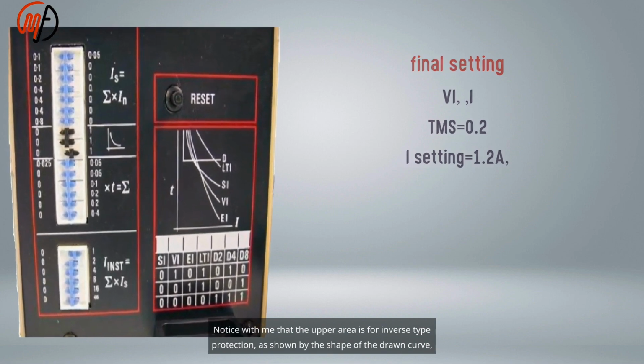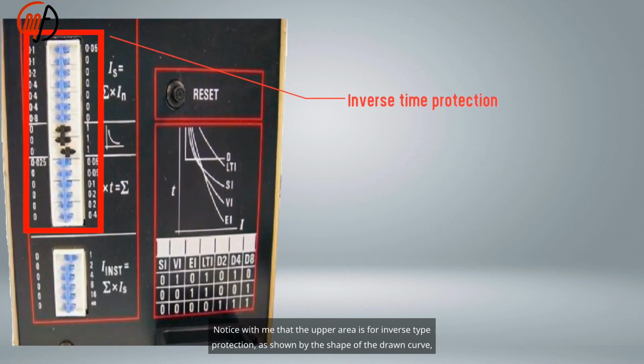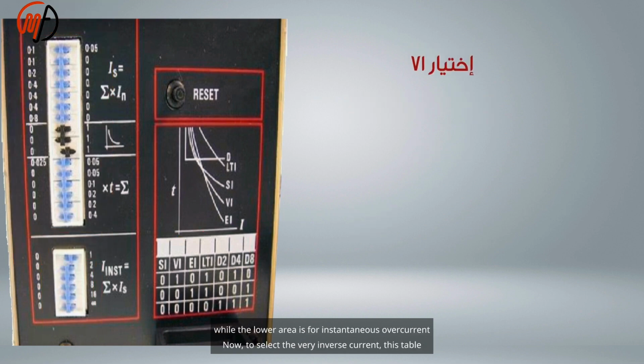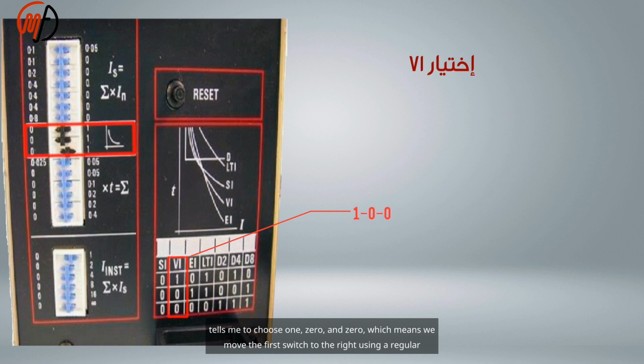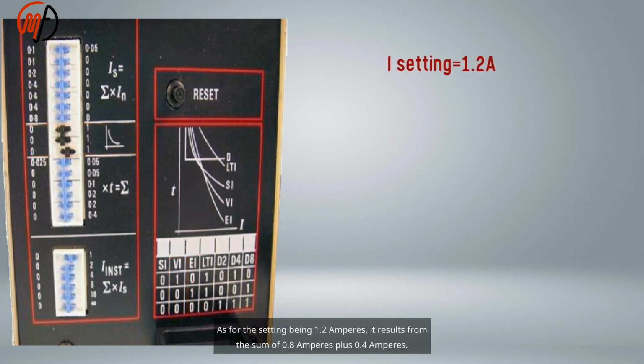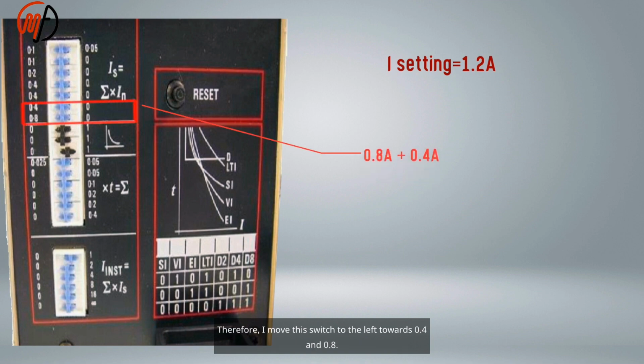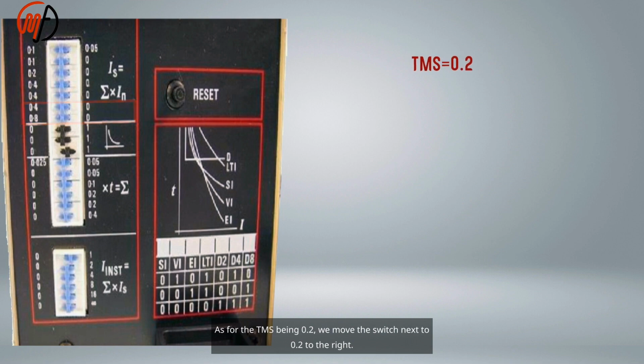Notice with me that the upper area is for inverse type protection, as shown by the shape of the drawn curve, while the lower area is for instantaneous overcurrent. Now, to select the very inverse current, this table tells me to choose 1, 0, and 0, which means we move the first switch to the right using a regular tool, and we move the second and third switches to the 0 position on the left. As for the setting being 1.2 amperes, it results from the sum of 0.8 amperes plus 0.4 amperes. Therefore, I move this switch to the left towards 0.4 and 0.8. As for the TMS being 0.2, we move the switch next to 0.2 to the right.